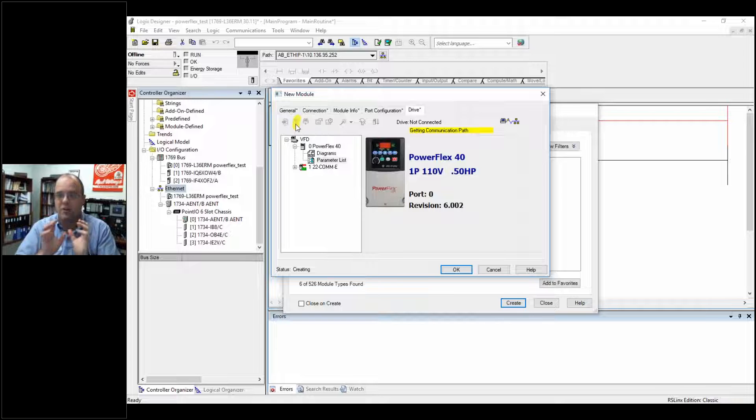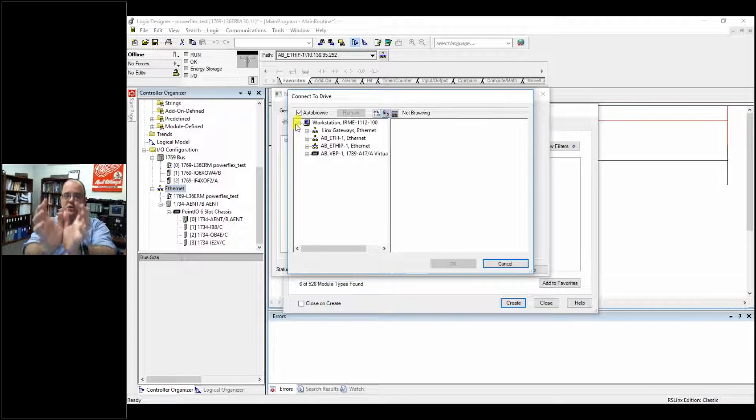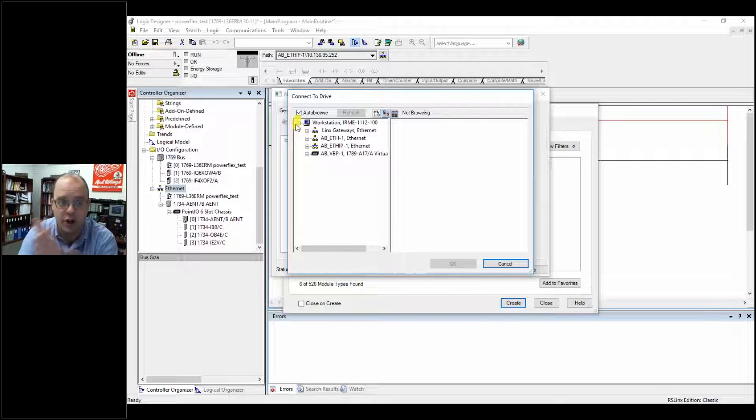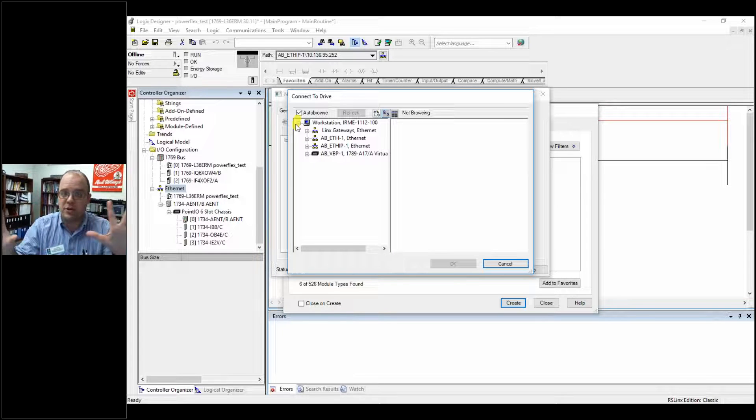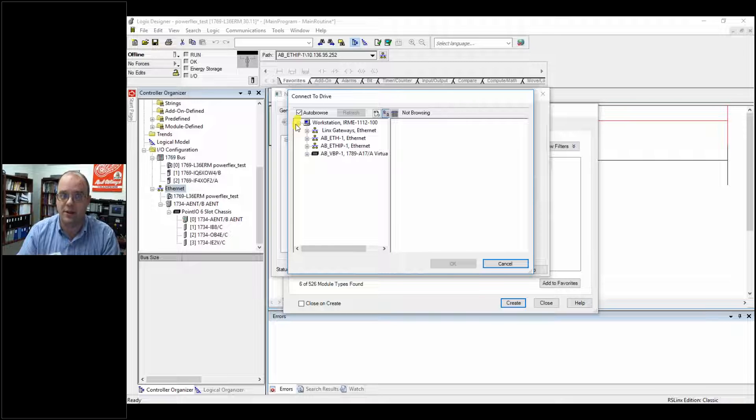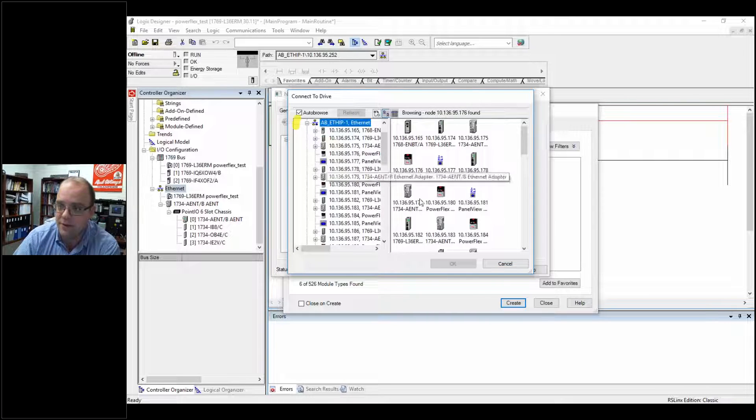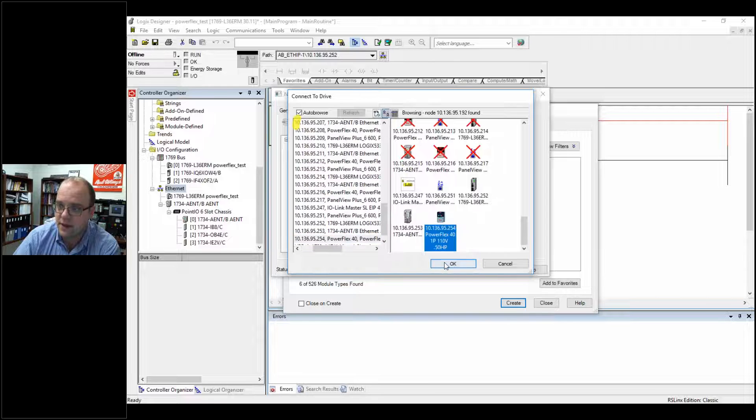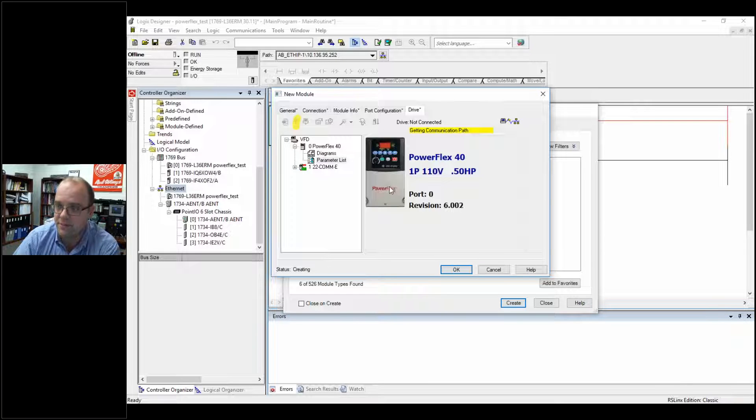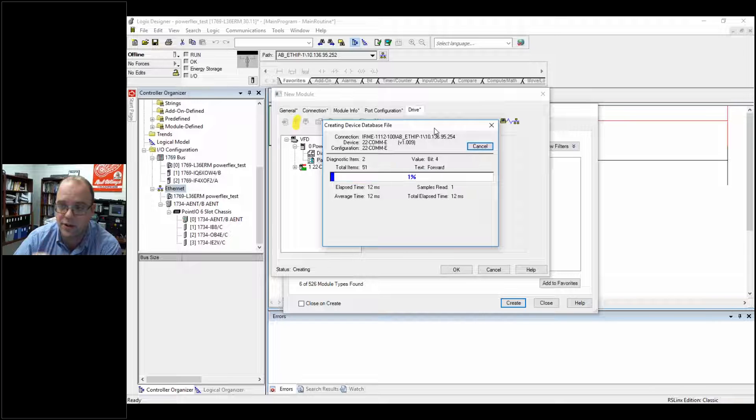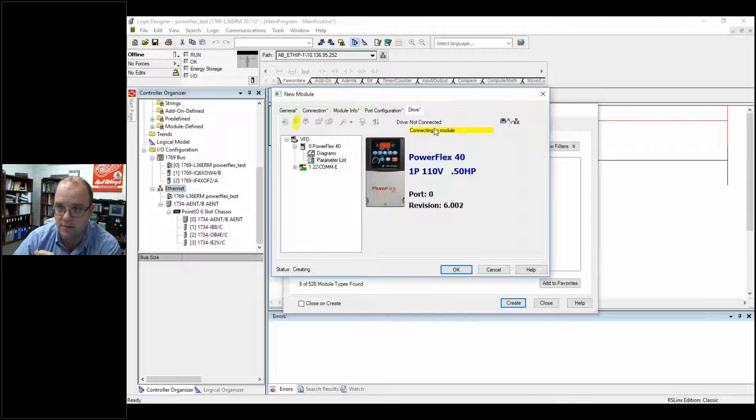Remember, we upload. We're taking the data from the drive and putting it in there. I would recommend doing that first. You can always change your parameters later. But at least it's getting your communication set up properly. So if I go in, I find my drive. Hit okay. And it's going to connect and bring in all your stuff, just like we would do a PLC. But we're uploading everything.